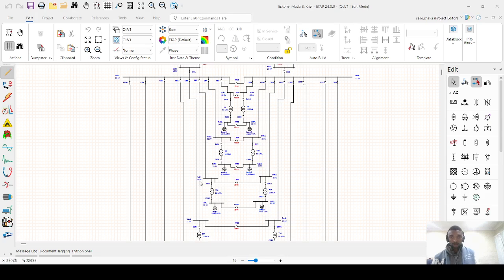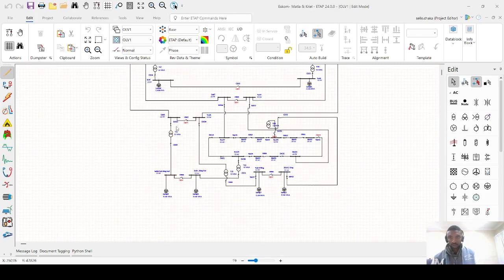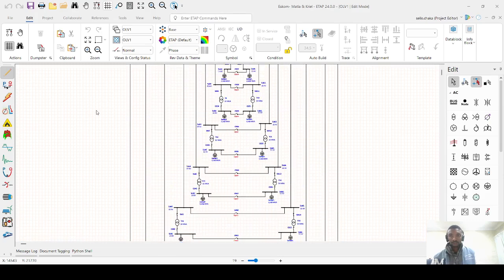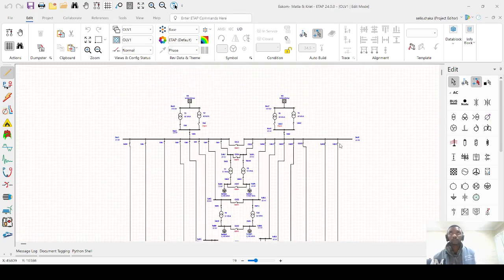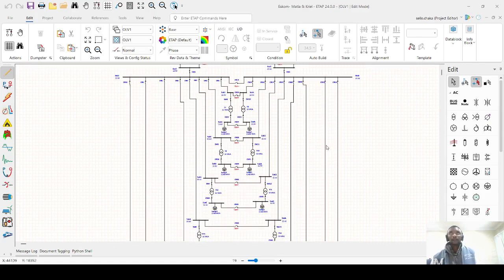Substation 1, 2, 3 up until substation 8 at 22 kV, also connected via these two 20 kV buses. Circuit breakers are used on all interconnecting feeders, enabling safe operations and the ability to perform N-1 contingency switching, whereby at least when we lose one feeder or transformer, it doesn't affect the entire system.